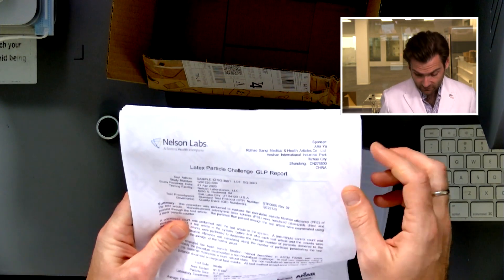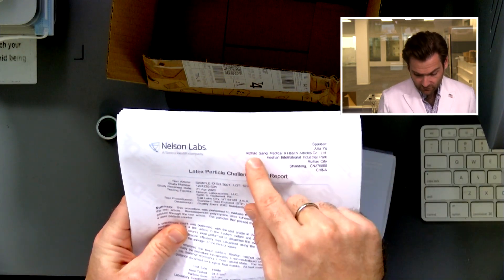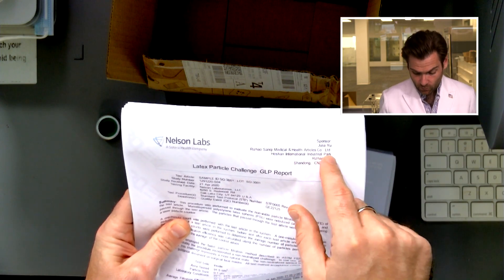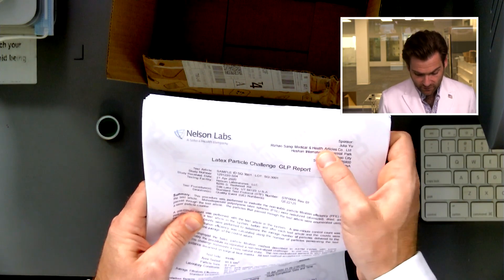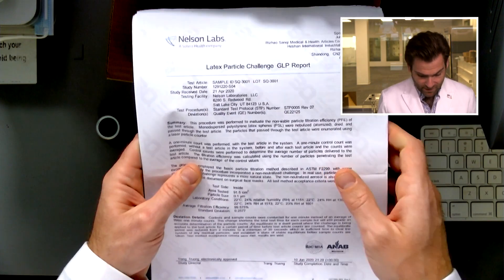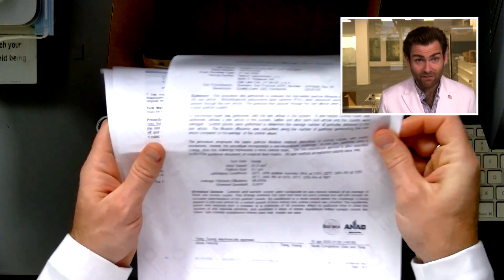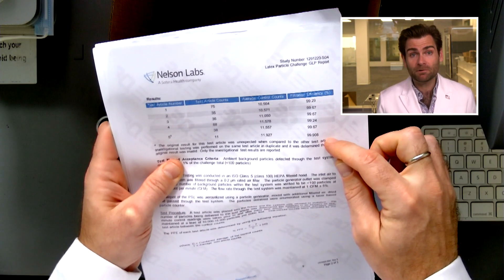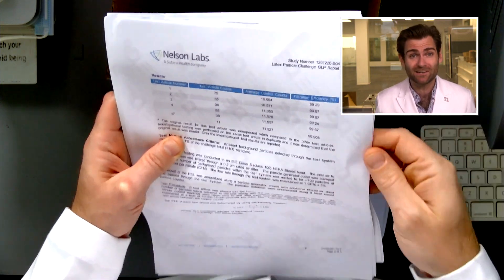They've actually sent their Nelson Labs report, and this is a legitimate report. It has the actual sponsor name with their location, the actual name — the Rizhao Sanqi Medical & Health Articles Co. — and they are showing on their test 99% efficiency. This is the same test that we are doing here.